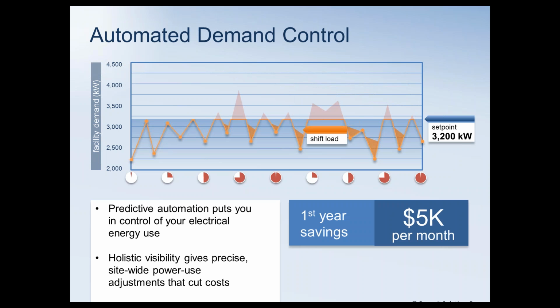With the automated demand control implemented, basically what we were able to do was take those high peak loads and shift them by 15 minutes into the next demand period. Because of the physics of melting, you still need the same number of kilowatt hours of consumption, but there again we're averaging that in so that it's smooth rather than a real high peak.